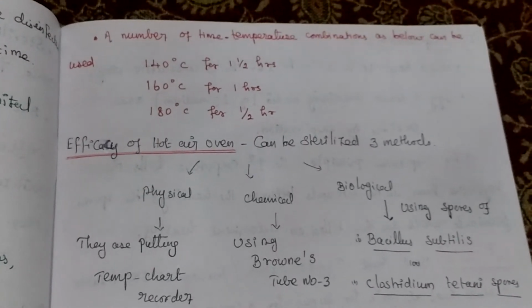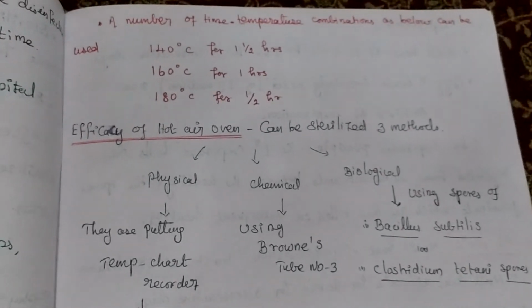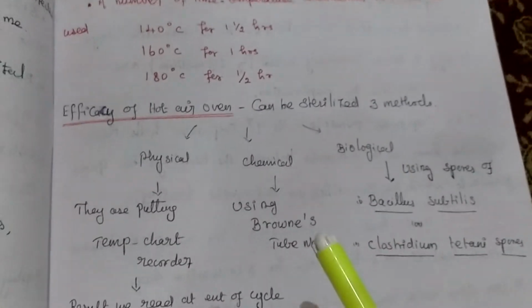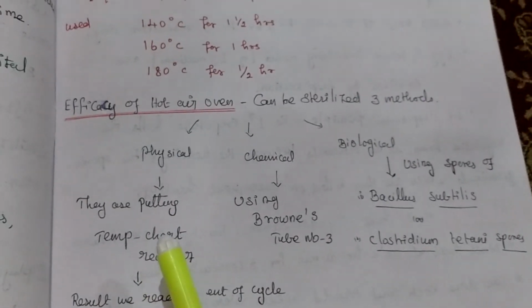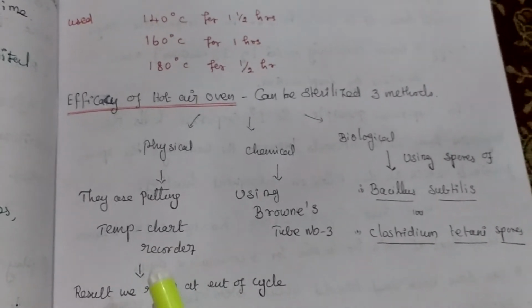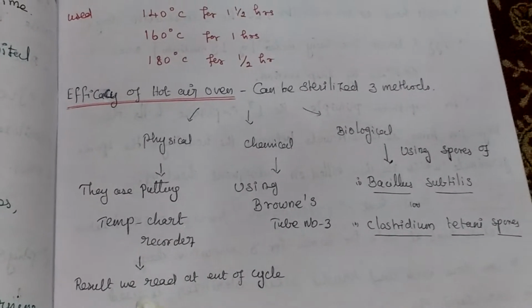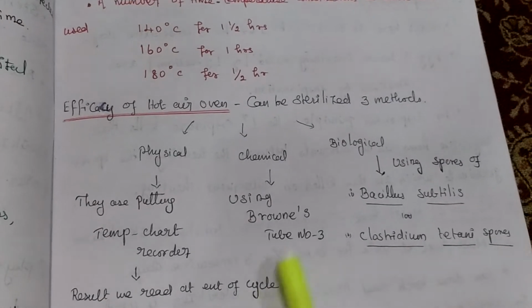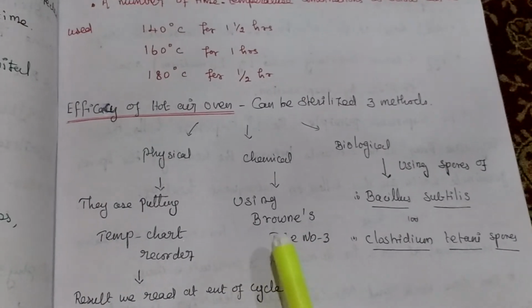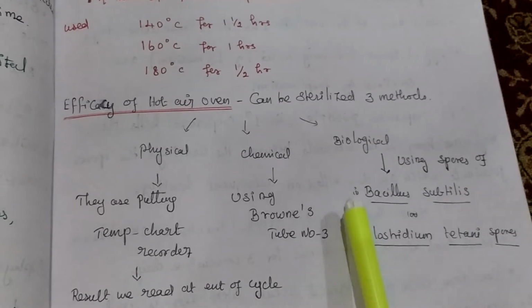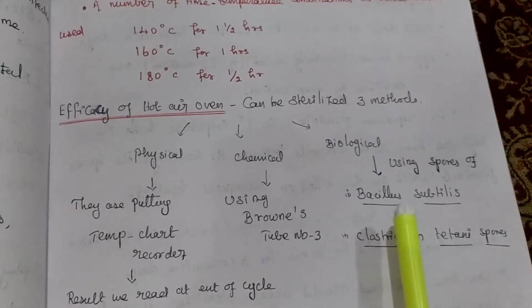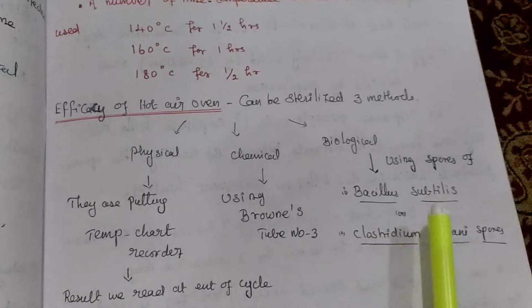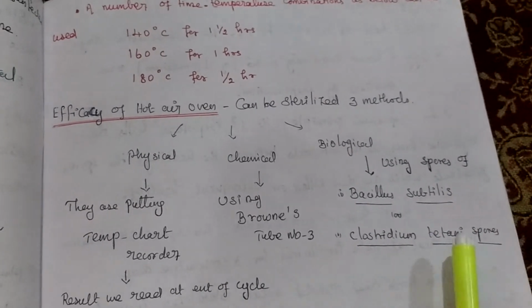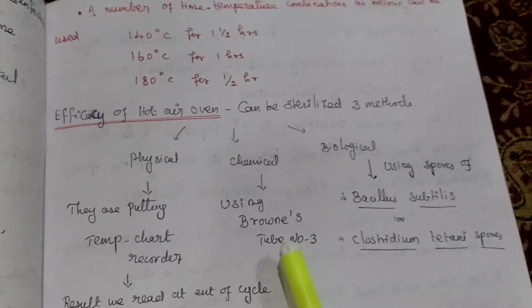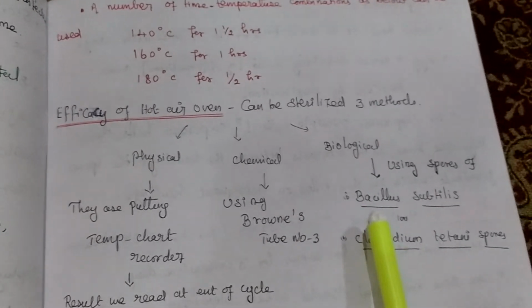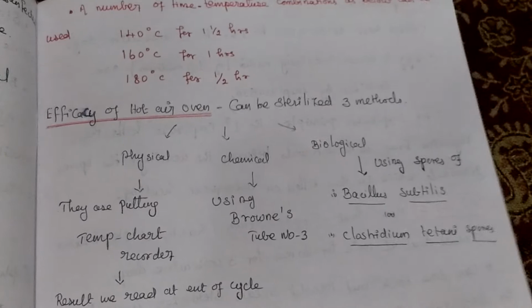Then the efficacy of the hot air oven can be tested by three methods: physical, chemical and biological. Physical method, there is a time-temperature chart recorder. The result we can read at the end of the cycle. Then the chemical method uses Browne's tube number 3. The biological method uses spores, Bacillus subtilis or Clostridium tetani spores.